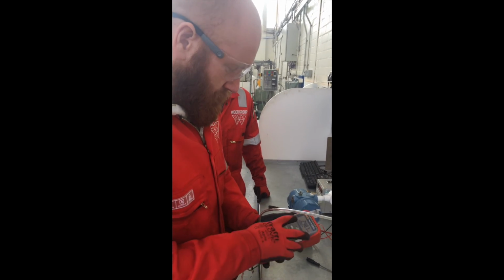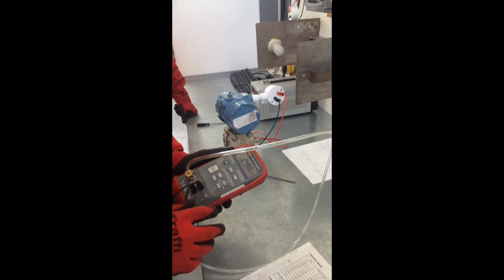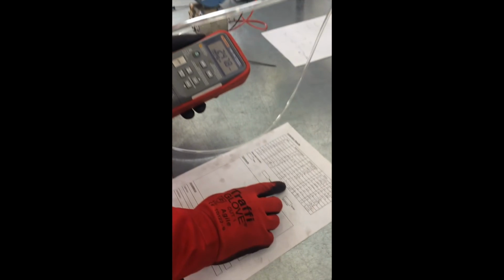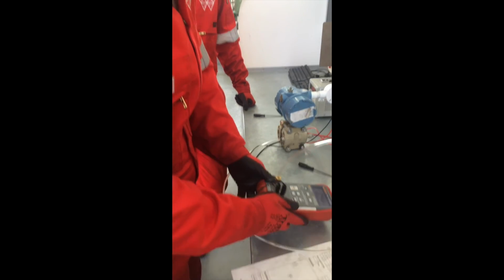The final reading we took was at 250. The pressure is dropping on it, like I said before, with the leak in the DP cell, so it's hard to get an exact reading at 250. So we took the reading at 250, we got the actual output to be 19.98, which is an error of 0.02, which is within the tolerance of 0.2. So all the readings are within the tolerance, so everything's calibrated to the values it should be.